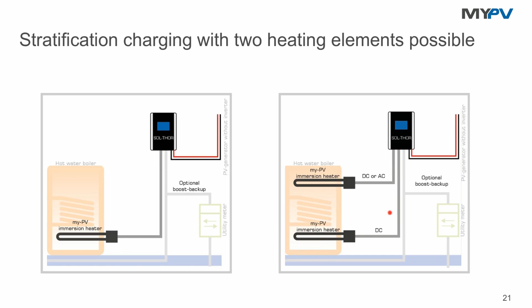And then when the heating here is finished, it changes over to the heater at the bottom and does the linear power control here. And one hint at this point, actually these 2 immersion heaters can also be in 2 different tanks. One can be in the hot water boiler, one in the storage tank. It does not matter. The AC backup, anyway, is just possible on the heater that has priority. So the heater on the top here in this schematic. Why is that? Good question. It's because in that way we ensure that the bottom side of the tank always is free for remaining PV power. So we are not going to block the boiler here with power from the grid. There's always a chance to have solar power for the heater.